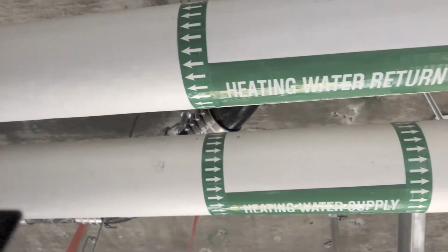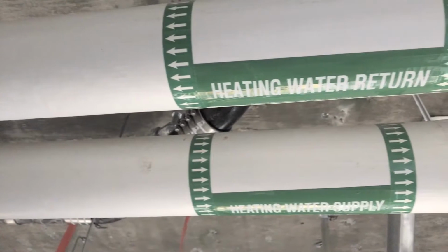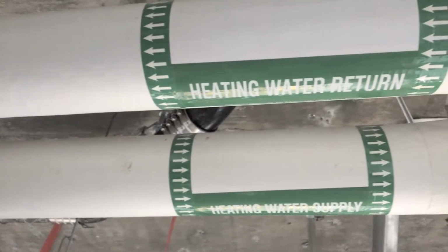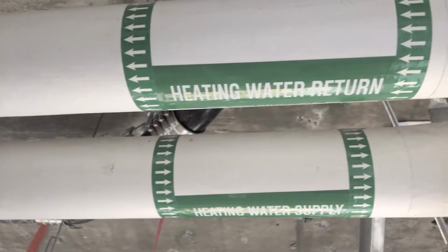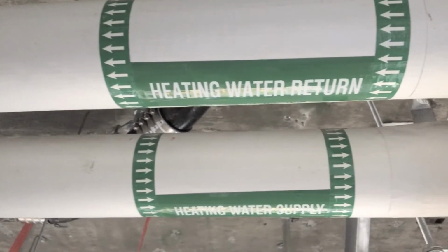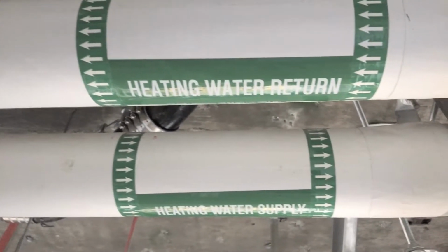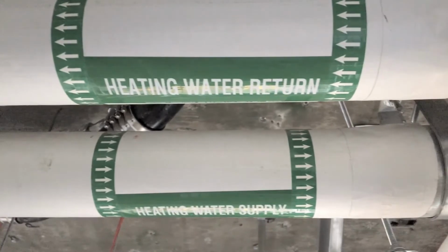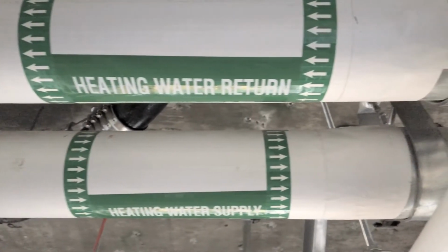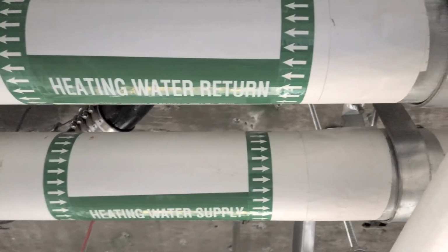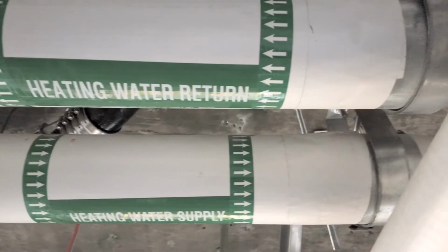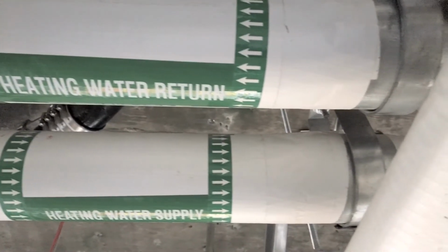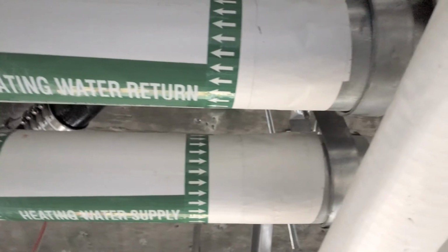Once the air has gone through the air handler, it is then delivered to the heating coils in their specific zone. Zoning allows for the independent control of separate building spaces, which will, in turn, help to reduce energy costs by using only the energy to heat or cool a zone when and where it is needed. This system uses a 2-pipe reverse return piping system, where the first terminal unit taken off the supply main is the last to connect to the return main. This is the tertiary loop in this building's hydronic system.